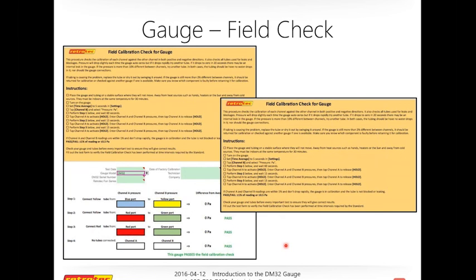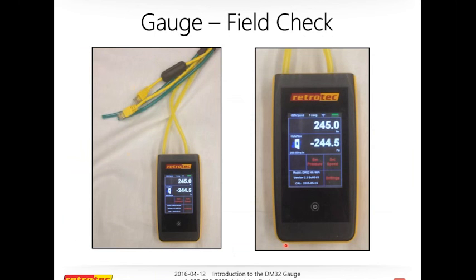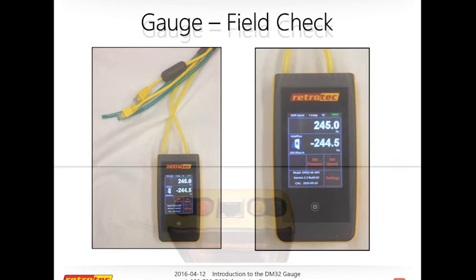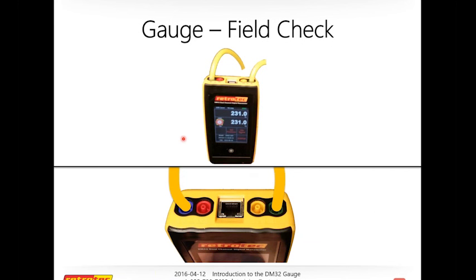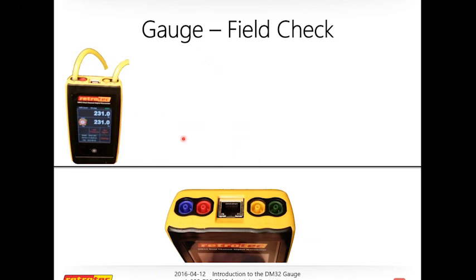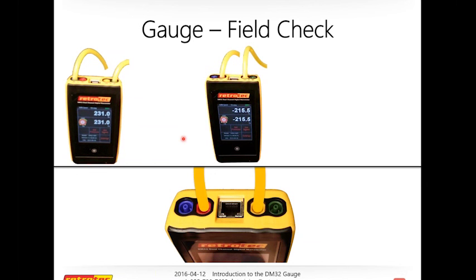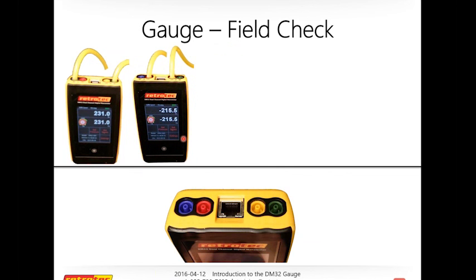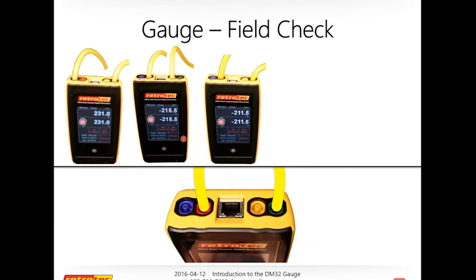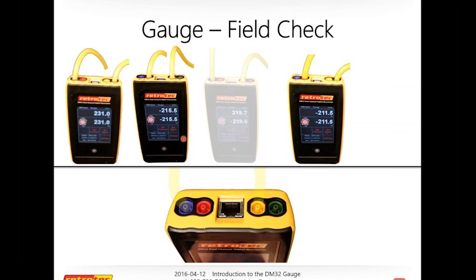So just a real quick test, and it's done something like this. This is the tubing from an umbilical of a duct tester, and we're using the yellow one. We recommend that you use the yellow one when doing the cross port tests, so that you have the same tube on each one. It's really simple. You basically test every possible cross configuration. So we're testing the inputs, now we're testing the references versus each other, now we're testing one input to one reference, and now one reference to one input.